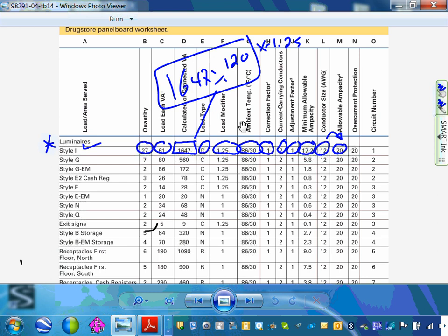Okay, it's coming. Now the overcurrent protection device right here. Now do me a favor, take the 17 here, this number, take it to 240.6, and that should give you 20 amps. Right? Yep. That's your OCPD. Standard ampere rating.